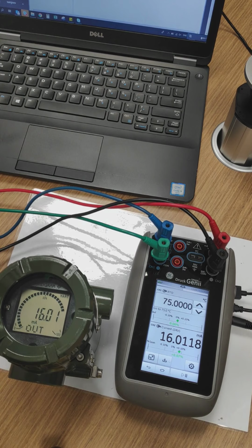Down 16 is fine. Wait for the settling time. Just observe the readings if you remember, and tell me if there is any hysteresis error. But we don't have to memorize with Foresight. Everything will appear on our system when we go back and upload the results.